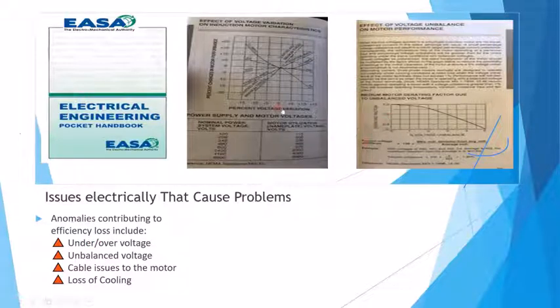This book basically shows you the effects of both unbalance, if all three phases aren't balanced, plus low voltage and high voltage. A lot of people don't realize that if you look at the factor, it shows here that if you have a 5% voltage imbalance, you're supposed to derate that motor to 75%. A lot of people will just look at the nameplate and say, well, it's a 1.15 service factor, I'm fine, I can run that. But we're basically putting everything at a stress point, which is a design nightmare. And you have the issue of imbalances, ABC, which cause the motor to draw too much current, so we get a cooling problem going on in the motor winding.